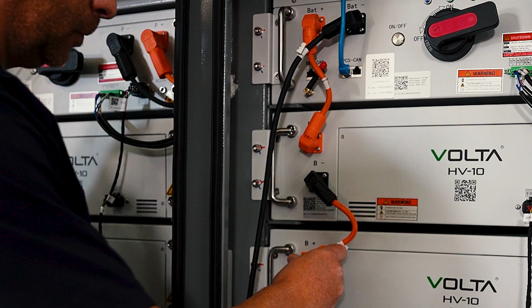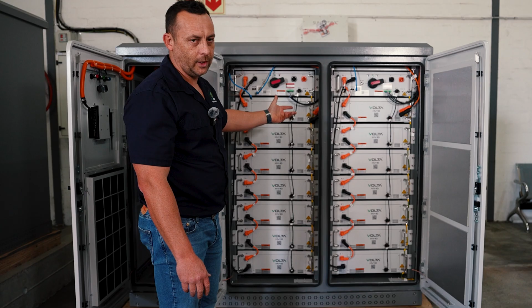And that's your first side done. Now for the second side. And guys, as you do the battery cables, just make sure that you hear a sufficient click. That means the terminals are fastened and secured. And that's it. Battery connections done. Also, you can see it's marked black and orange. You cannot insert the terminals at the incorrect place, unless you force it, then you will blow up your batteries. So just make sure that black goes to black, orange goes to orange. And remember, this is series, not parallel.